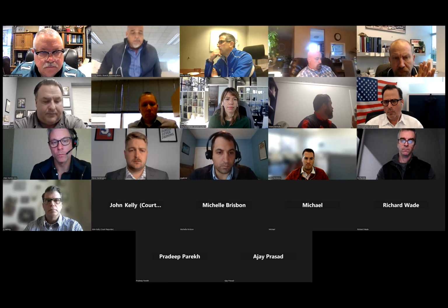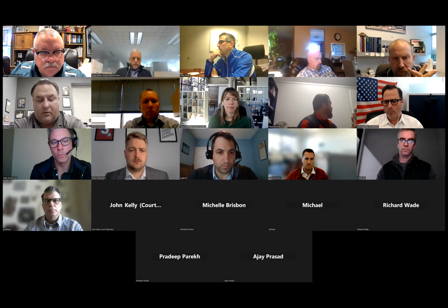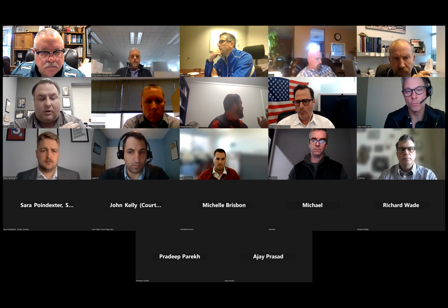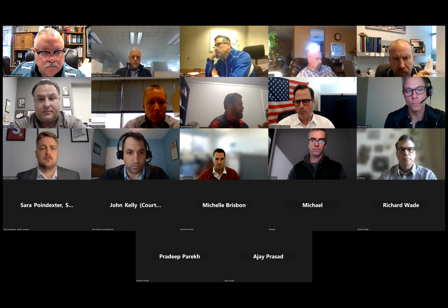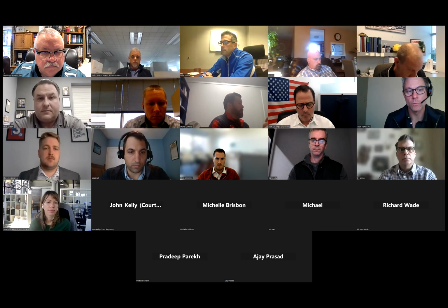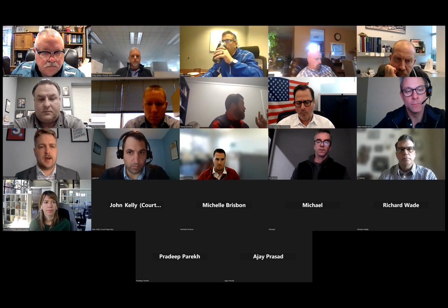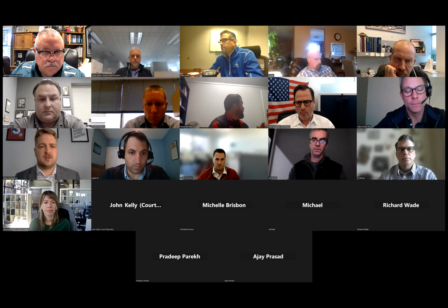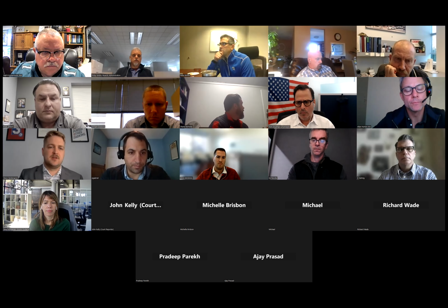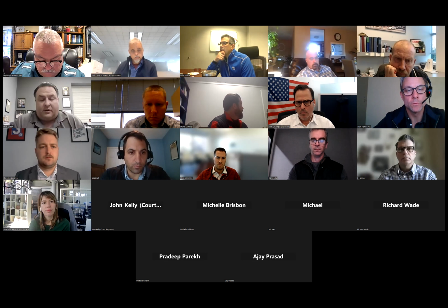With the BAS, you are proposing that there's an alarm that alerts the BAS. Does the BAS alert either a building engineer or alert in the building engineer's office? I am not the controls engineer on the project, but I believe so. Based on boilers within the building, it is a fully staffed maintenance building. And so that alarm would either be in the staffed office, or I believe there's optionality for that to alert a text message to the head of building maintenance and then building engineering. So it would be constantly monitored.